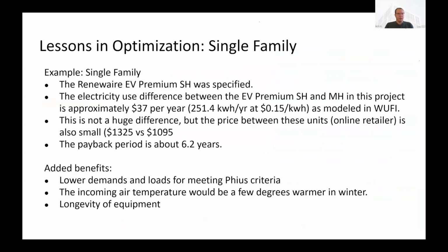All right. One other last point in the single family. This is just a different project that had this Renewaire EV Premium SH specified. And I did a calculation looking at the Premium S and the Premium M and saw that the difference was approximately $37 per year, or 251 kilowatt hours per year at 15 cents per kilowatt hour as modeled in WUFI. It's not a huge difference, but the price between those units at an online retailer was also pretty small, 1325 versus 1095, and it led to a payback period of about 6.2 years. So this is just going up from the S to the M. There is a cost associated with that, but this shows that the payback period is pretty reasonable. Actually, 6.2 years. You would hope that your ERV is lasting longer than that.